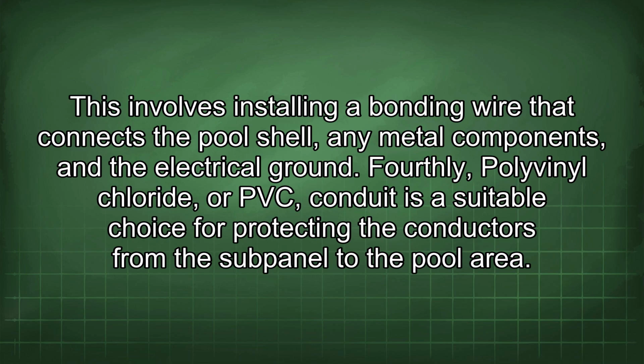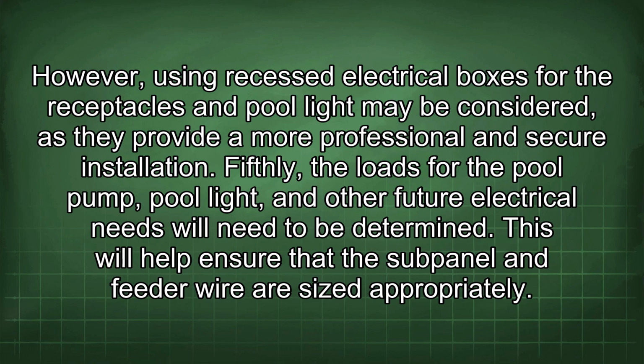Fourthly, polyvinyl chloride, or PVC, conduit is a suitable choice for protecting the conductors from the subpanel to the pool area. However, using recessed electrical boxes for the receptacles and pool light may be considered, as they provide a more professional and secure installation. Fifthly, the loads for the pool pump, pool light, and other future electrical needs will need to be determined. This will help ensure that the subpanel and feeder wire are sized appropriately.